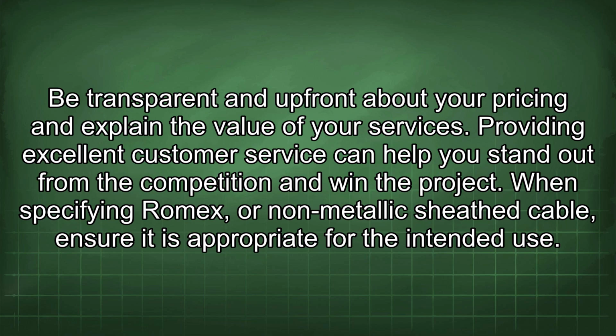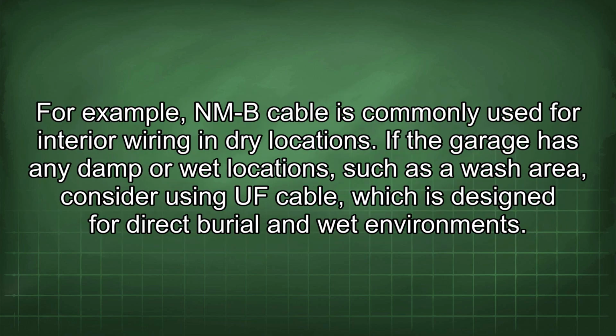When specifying Romex or non-metallic sheath cable, ensure it is appropriate for the intended use. For example, NM cable is commonly used for interior wiring in dry locations. If the garage has any damp or wet locations, such as a wash area, consider using UF cable, which is designed for direct burial and wet environments.